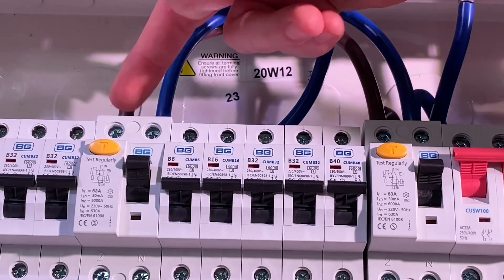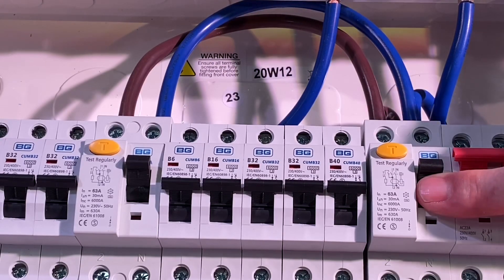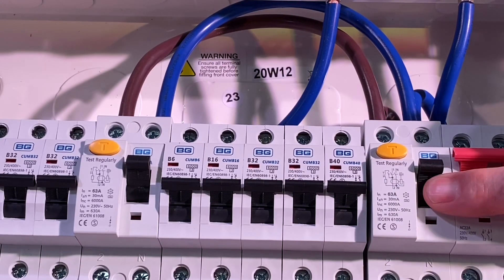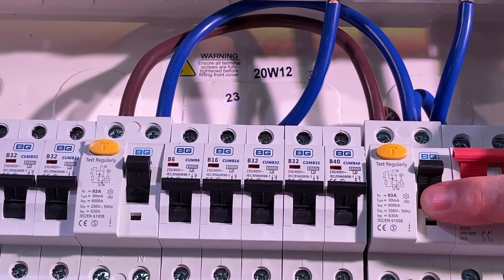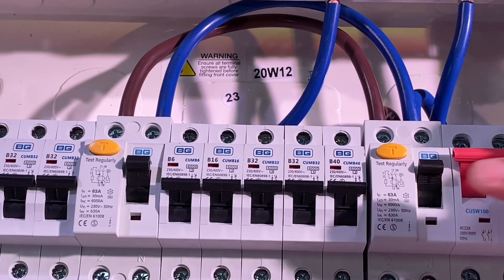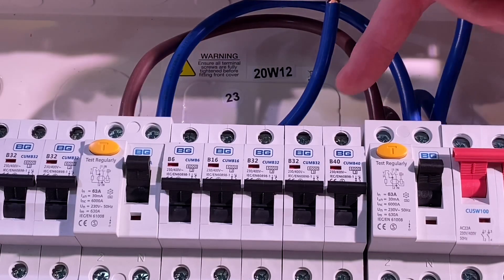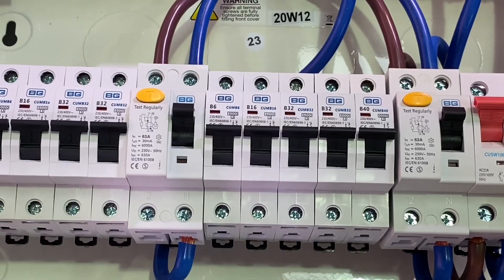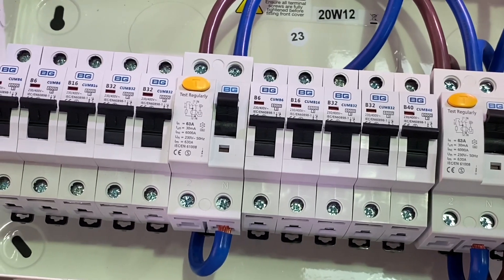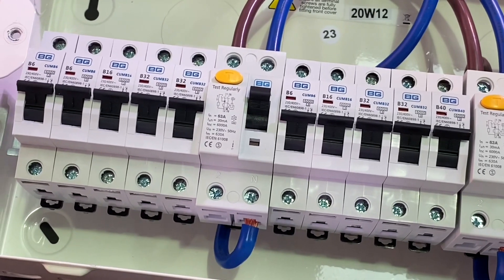Let's first look at the two RCDs. They're both rated at 63 amp, both type A RCDs and are rated at 30 milliamps to offer additional protection. The board comes fully loaded with 10 breakers, all B-type. It comes with 1x40, 4x32s, 2x16s and 3x6-amp breakers.